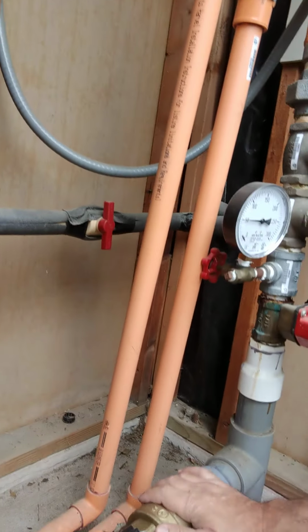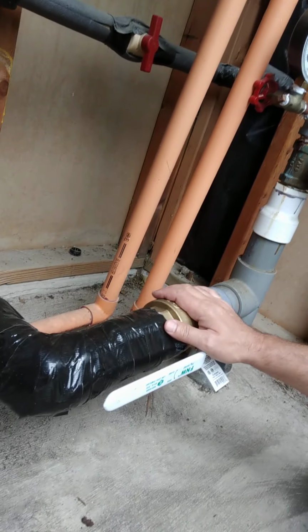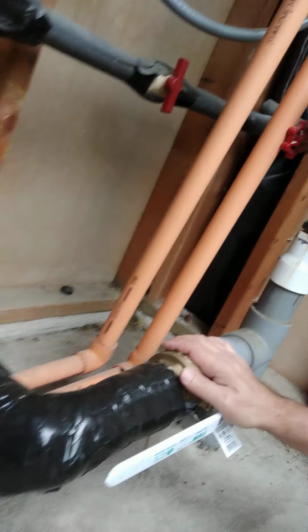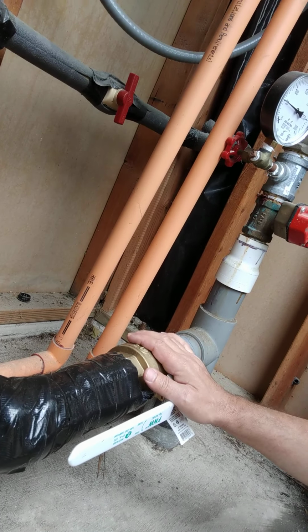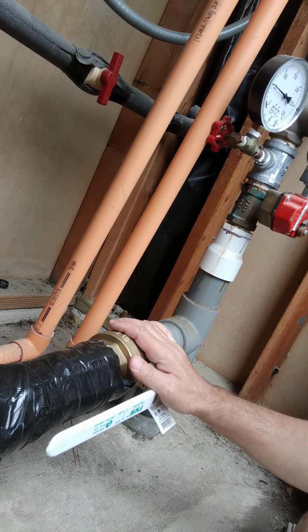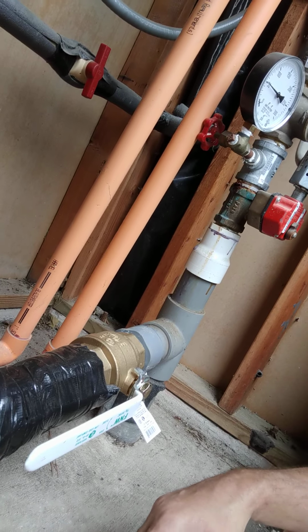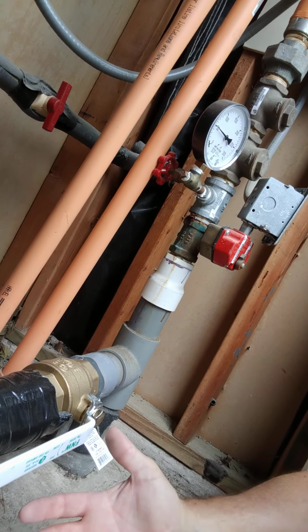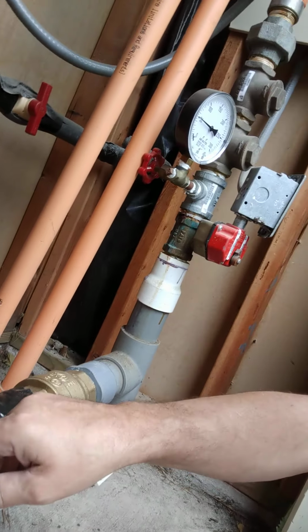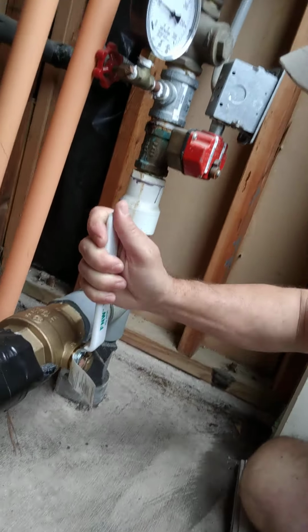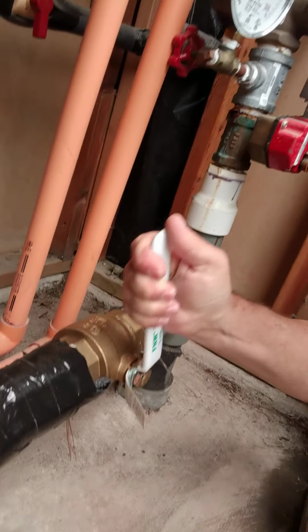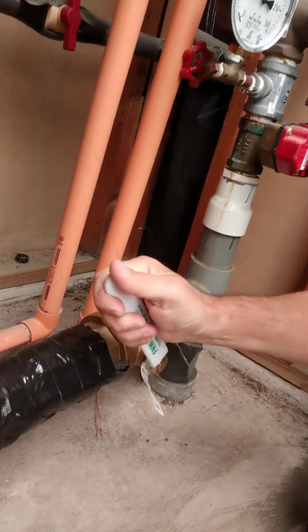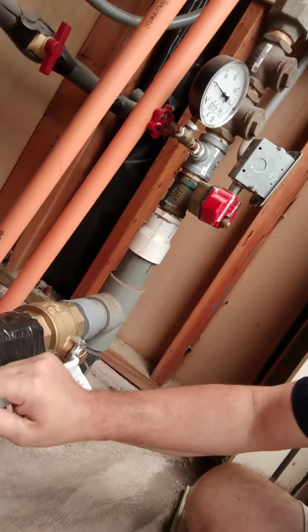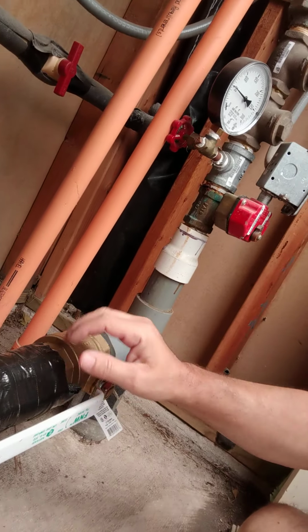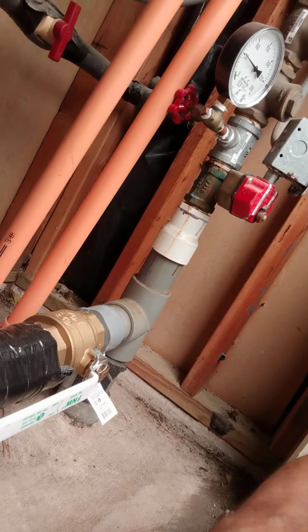Real important here, your main valve for the entire building, these things go bad, and it's mostly from a lack of use. So at least every 3 months at the most, come and exercise your valves 2 or 3 times, and if you do this, then your valve should be ready for you next time you need to use it, and you won't have one that doesn't want to close completely.